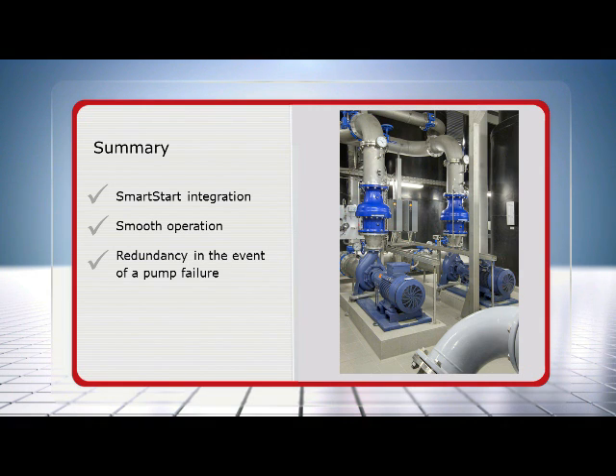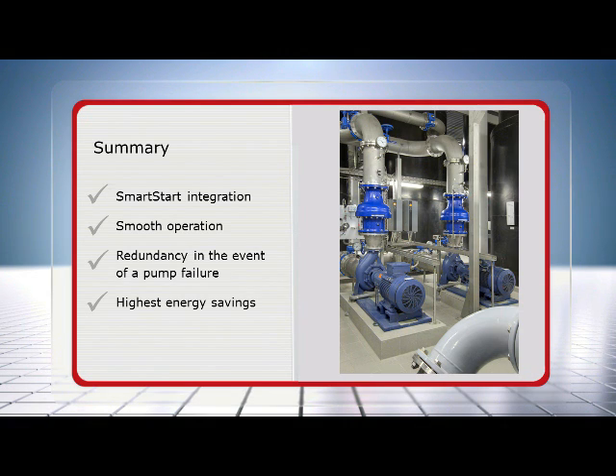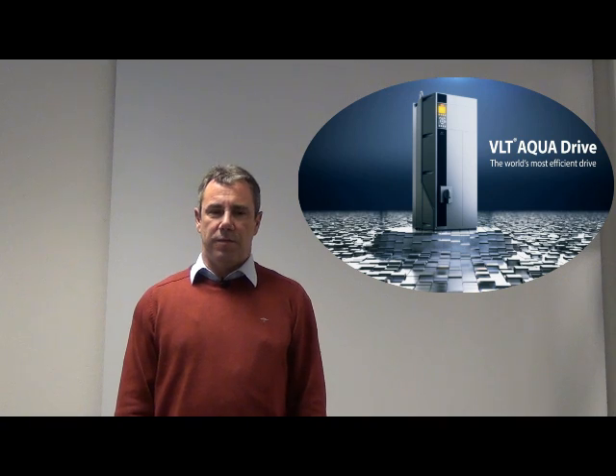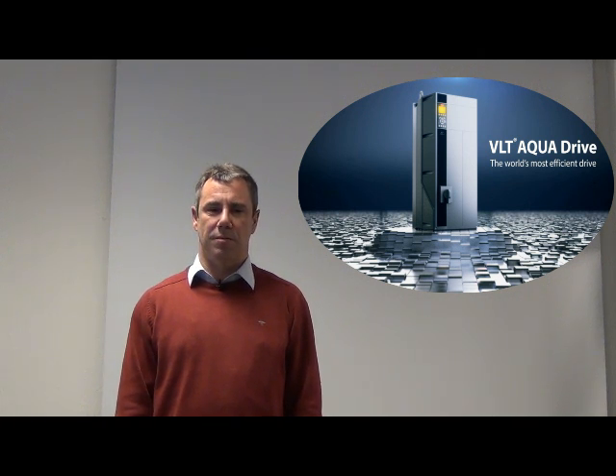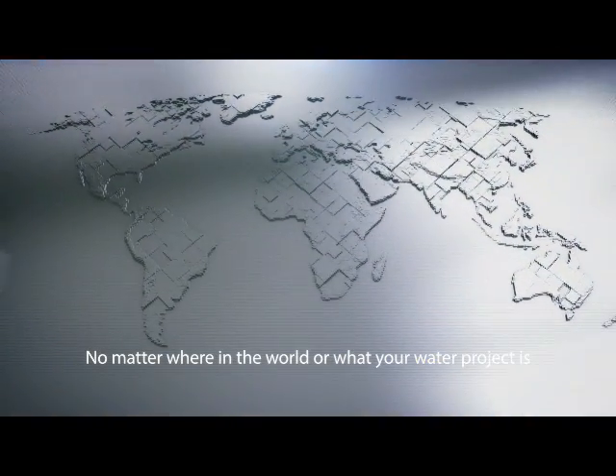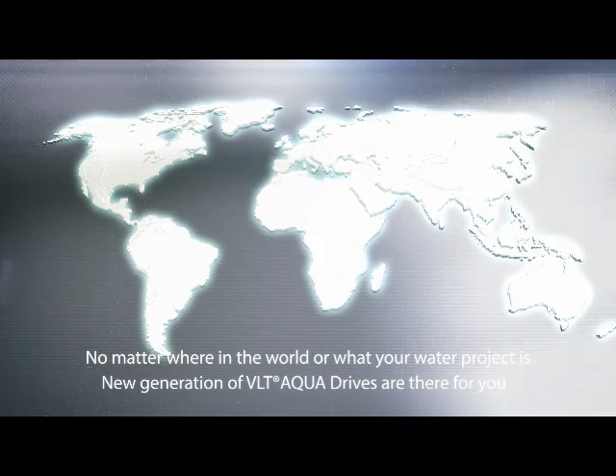In the event of a pump failure or if a pump is disabled for maintenance, the cascade controller will try to compensate for the missing pump. In a master follower application all pumps run at the same speed. Sharing the load between the pumps in the system ensures a highly efficient operation. Load sharing also saves energy by continuously monitoring the energy consumption and adapting the staging speeds if required. Thank you for joining me today. We invite you to contact your local Danfoss supplier or to visit danfoss.com/aquadrive for more information. No matter where in the world or what your water project, new generation VLT AquaDrives are there for you.